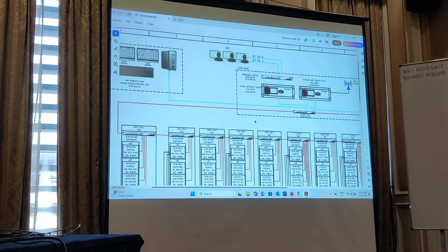Just now the one at the bottom is horizontal. Right, horizontal type. From bottom to top is vertical. So vertical is basically MMS. Horizontal is basically goose. MMS is just information being sent, but goose is transmitting and receiving. So how this goose transmits and receives, as you can see from the topology, is a ring topology. The fibers enter the ESM, and then the ESM acts as a router. That router connects all the ESMs together.